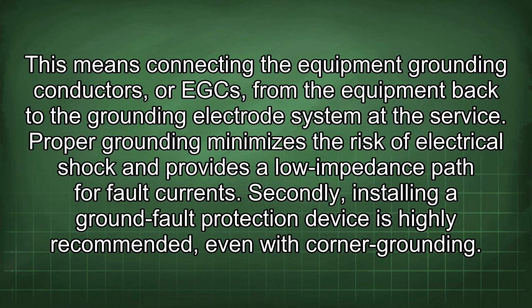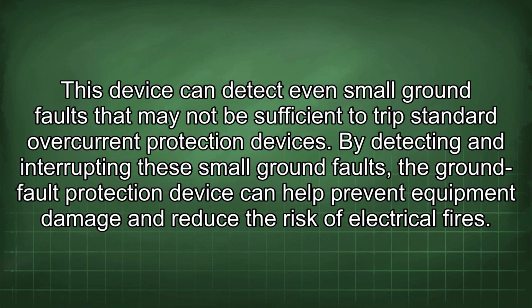Secondly, installing a ground fault protection device is highly recommended, even with corner grounding. This device can detect even small ground faults that may not be sufficient to trip standard overcurrent protection devices. By detecting and interrupting these small ground faults, the ground fault protection device can help prevent equipment damage and reduce the risk of electrical fires.